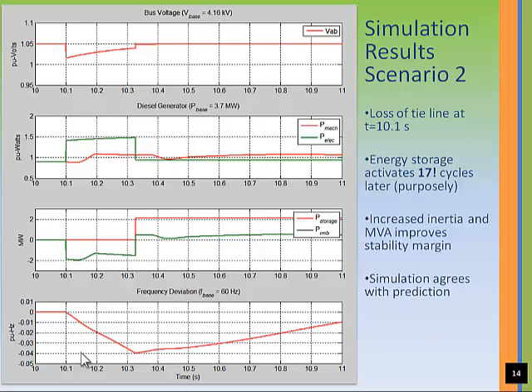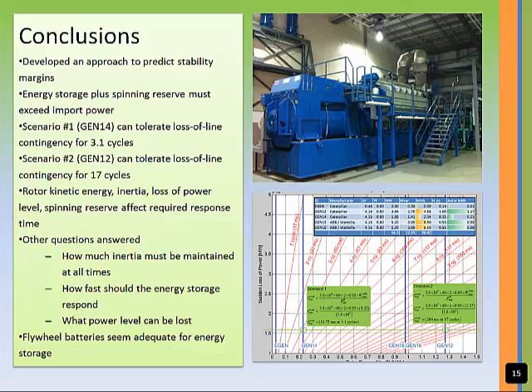The bottom chart shows that the frequency remains bounded by 5% despite the 17 cycle wait time. Waiting 17 cycles is an exaggeration. However, the exercise here is to predict how long a generator can withstand the contingency and validate the predictions of slide 12. A method that shows how long a generator can sustain a frequency on its own was presented. The method shows predictions in terms of frequency stability margins. The equation was validated using two simulation scenarios.